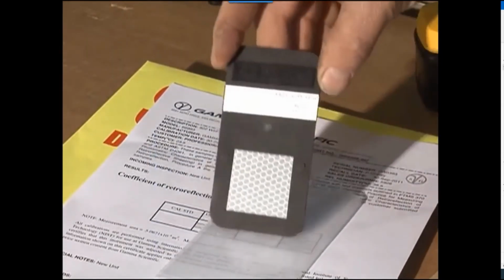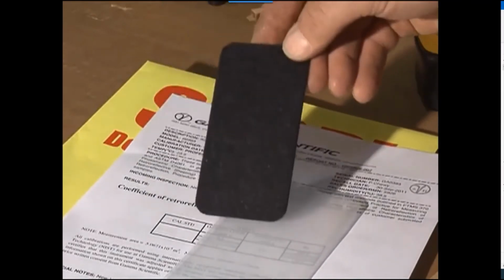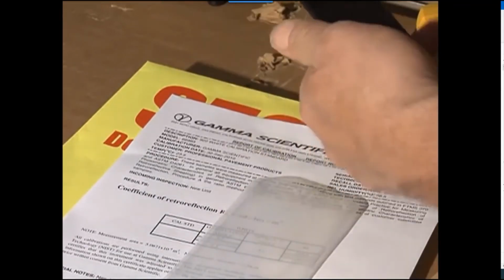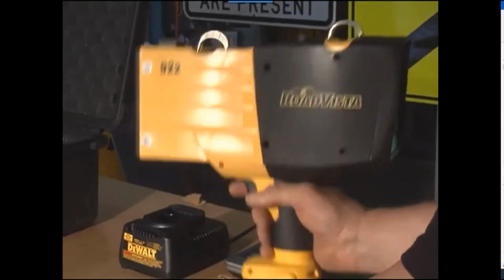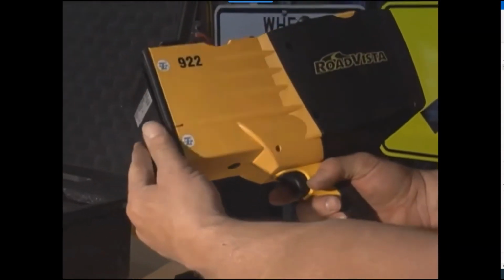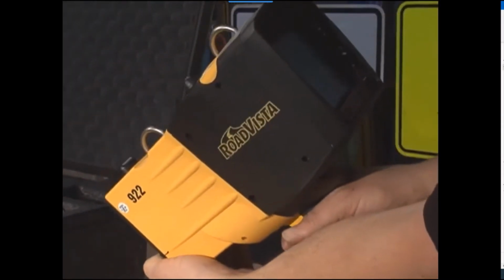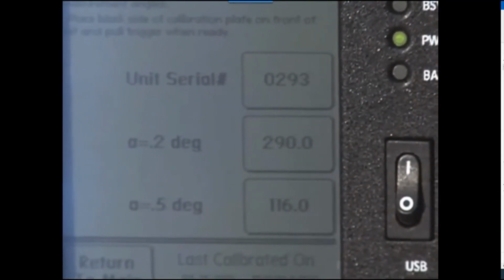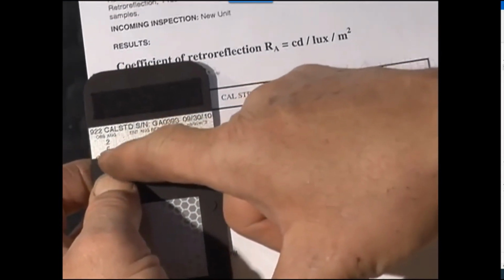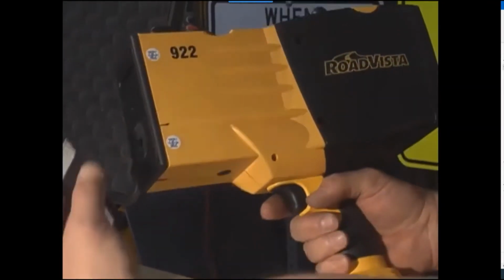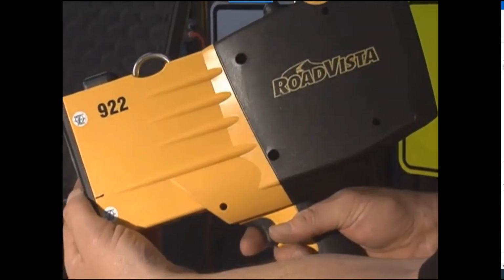Remove the calibration standard card from its protective cover. Handle the card by its edges, being careful not to touch either face of the card where it is measured. Verify that the calibration values and the serial number displayed on your screen match those on your calibration standard card. Place the black or 0 side of the calibration standard card. Pull the trigger until a beep sounds.